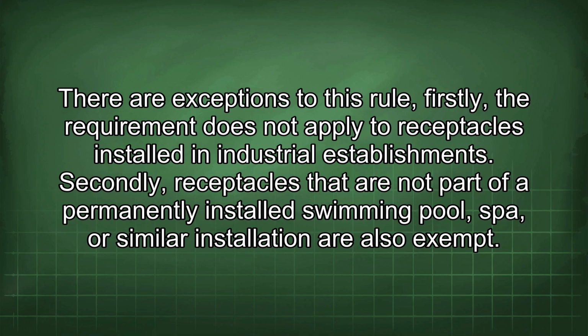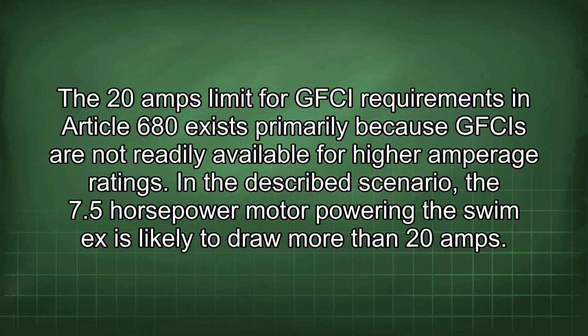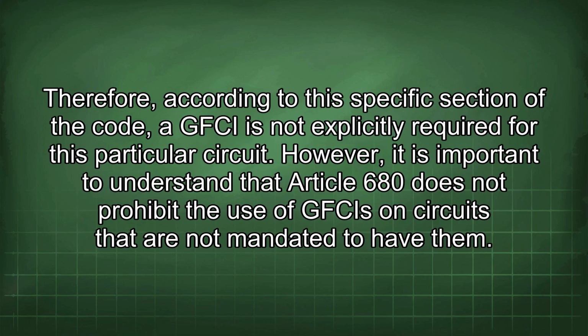Firstly, the requirement does not apply to receptacles installed in industrial establishments. Secondly, receptacles that are not part of a permanently installed swimming pool, spa, or similar installation are also exempt. The 20 amps limit for GFCI requirements in Article 680 exists primarily because GFCIs are not readily available for higher amperage ratings. In the described scenario, the 7.5 horsepower motor powering the SwimX is likely to draw more than 20 amps. Therefore, according to this specific section of the code, a GFCI is not explicitly required for this particular circuit.